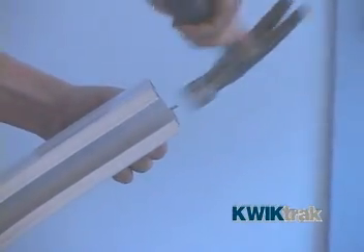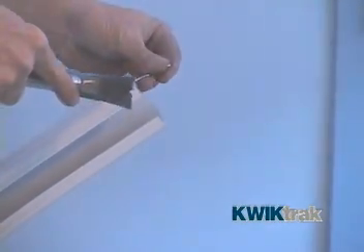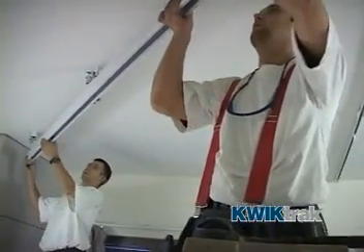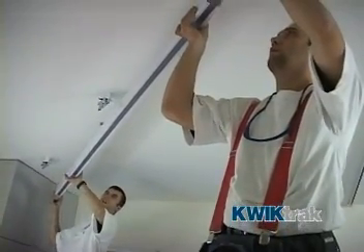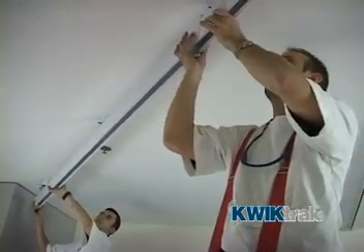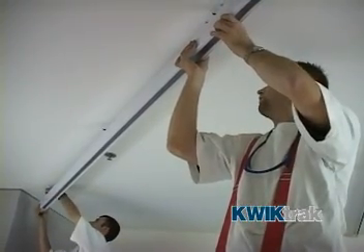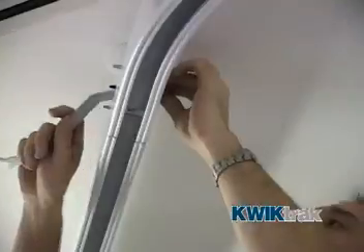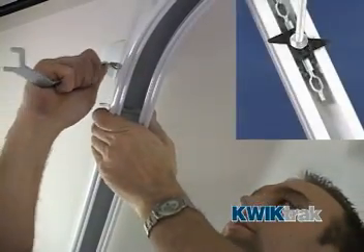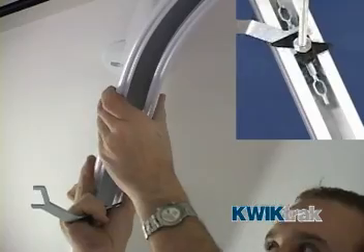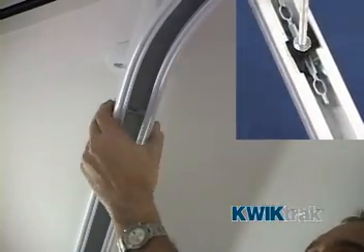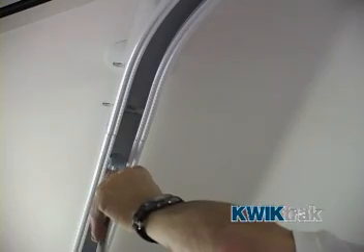Track joints are prepared by setting spring pins in the lower channels of one of the track sections. Track sections are snapped up in place on the installed brackets. Using a specialized wrench, the black bracket cam is rotated 1/4 turn, locking the track to the ceiling bracket. At track joints, the spring pin tool is used to tap both pins along the channel until they span the joint, ensuring perfect alignment.